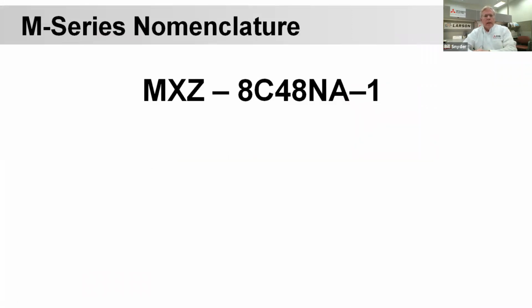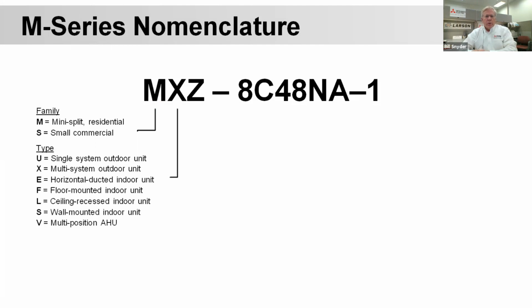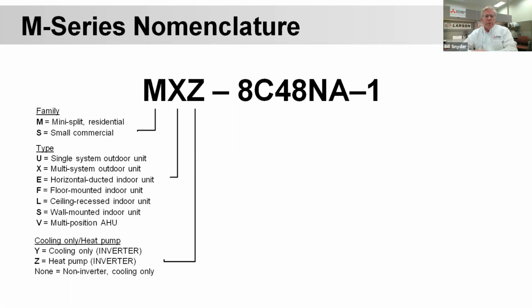Okay, so now we're talking about the M series nomenclature and how the model number populates and so forth. So the first thing we're going to talk about is the M here. It could be an M or an S. It's a mini split, small, light commercial, or mostly residential application starts with an M. And the next digit would indicate whether it be a single system outdoor unit like an MUZ or an MUY, which are the outdoor units. But if it was an MSY, for instance, that would be a wall-mounted indoor unit, or an MV is a vertical air handler, that sort of thing. And the Z would indicate inverter heat pump, or if it was a Y, it would be cooling only.